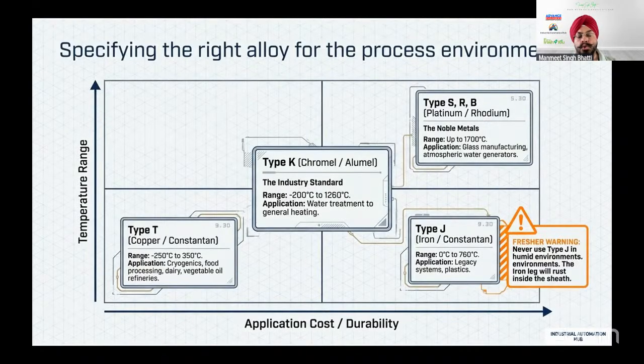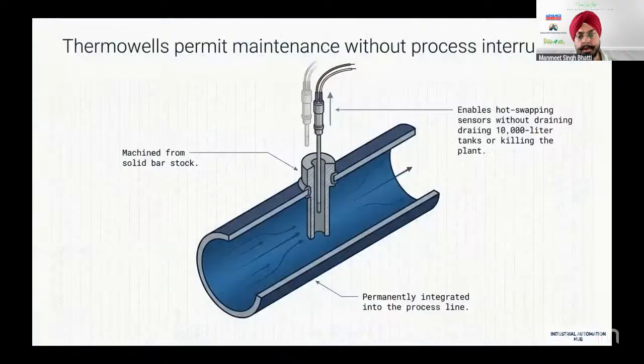If you want to use a K-type thermocouple, which is mostly used in the industry, you can definitely use that. But lots of industries are also using J-type. So J and K are mostly used in the industry, but you can also go for rhodium base, and you can also go for type T if you're going in for a very high level of cryogenic application. So these are the main ones, make a note of this. You can understand that this is the reason people are using these kinds of thermocouples.